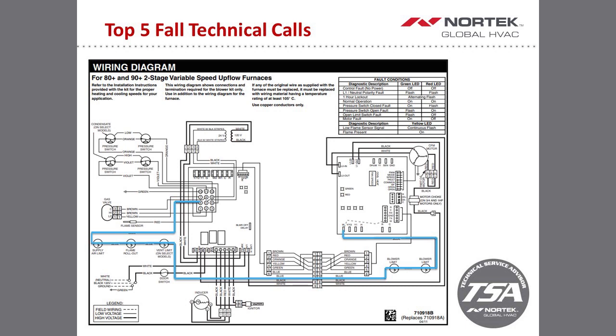And again, we only recommend this for testing where we're trying to nail down a potential false code situation. The next topic that we have here is in regards to furnace boards. So normally how it goes into tech on this kind of call is guys will call in, they'll give us a scenario and they'll say we've replaced the circuit board and we're still getting the same fault code or the same situation and it hasn't been changed.